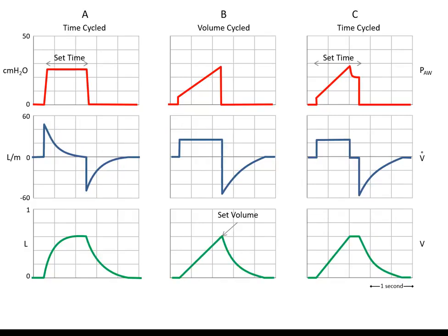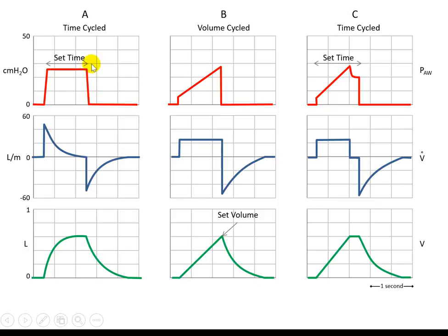The third variable is how the breath is ended. The first was the initiation of the breath, the second was the limitation of pressure, flow, or volume between initiation and end, and the third variable is the end of the breath — what we call cycling, or changing from inspiration to expiration. You can set a time, and once that time has elapsed, the pressure is released and the breath ends. This would be time cycled, as opposed to cycling based on volume.